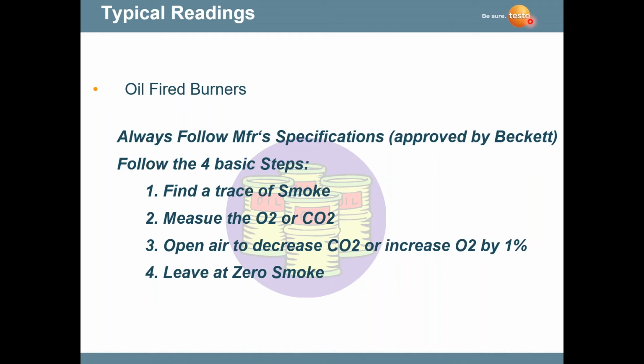Now, I do know you guys have a lot of oil burners up in Canada. Here in the Southeast, we don't, but we do have it in parts of the United States. I work a lot with Beckett, and as you know, they're a US manufacturer of burners. They have 4 basic steps for using a combustion analyzer. Number 1, they want you to find a trace of smoke first. How we find a trace of smoke is using not a digital instrument, but a smoke pump, similar to a bicycle pump, where you're pulling flue gases through filter paper and matching that filter paper up to a scale.